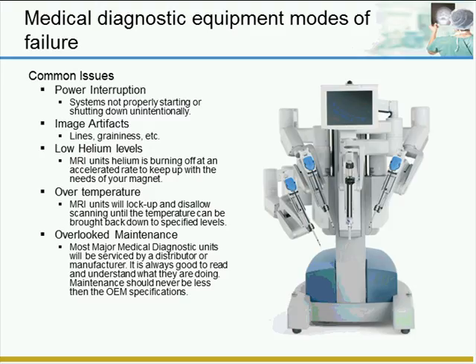Low helium levels on MRI units are common. It's important to monitor your helium levels. Most MRI service contracts won't cover a magnet quench due to negligence. I believe helium levels are supposed to be around 70%. Anything at 50% and under is critical to get more helium into the system. A quenched MRI magnet could result in magnet failure and millions of dollars in repair costs and downtime.